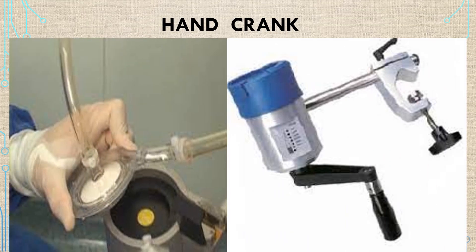Complications of the pump include pump thrombosis, pump failure, retrograde flow, and air embolism. Another part of the ECMO circuit is the hand crank, which works manually when there is pump failure or power failure and can be used until the problem is resolved.